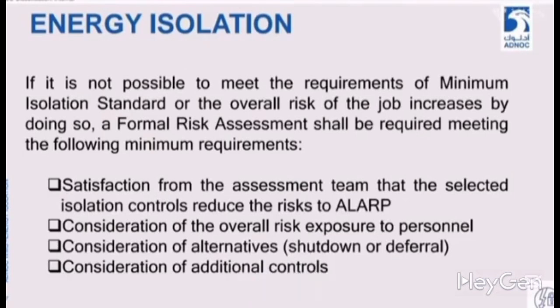We need to consider the risk within the framework of the FRA that our people might face if we are not controlling the isolation to a minimum standard. If there is an energy leak, exposure, or restoration, what will be the risk level of exposure for our people? The next step is the consideration of alternatives, shutdown or deferral. We should shut down a piece of equipment. We cannot isolate the source of supply from where it is coming, so we need to shut it down from there and temporarily defeat it.